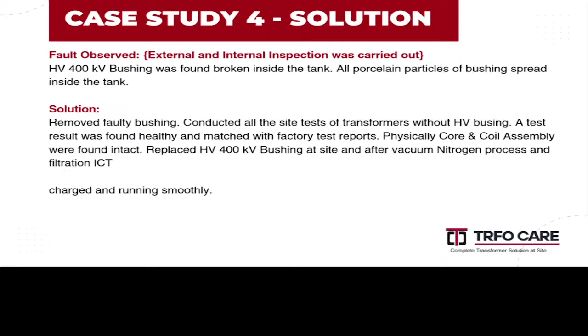This is the condition inside the transformer. You see a lot of insulation particles, and the condenser of the bushing, everything is inside the tank. We removed the bushing, and luckily a bushing was available at site. We replaced that bushing and tested the transformer. This is also running successfully for the last 8 months. These are the various case studies I am showing you. This one is special.